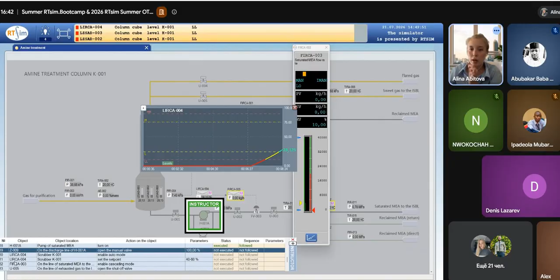And we watch now that the column cube is filled and the flow rate on the column is being established. As you can see, soon it will come to the normal position. Okay, so far there is only monoethanolamine in the column. We didn't, as you remember, open yet and direct gas to the column for cleaning, because first the column cube needs to be well filled. This needs to be done for a good gas cleaning, so we will wait until the cube is 50% full.